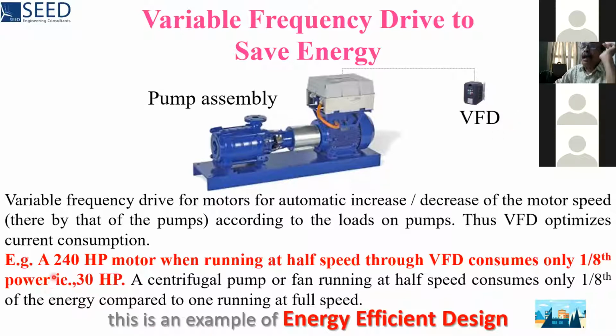See an example. A 240 HP motor, when running at half the speed through a variable frequency drive, consumes only 1/8 of the power. That means when it is running at 50% speed, instead of a 240 HP motor, it is acting like a 30 HP motor. So a centrifugal pump or a fan running at half speed consumes only 1/8 of the energy compared to the one running at full speed. So that is an example of energy efficient design. Let us see a video on this subject.